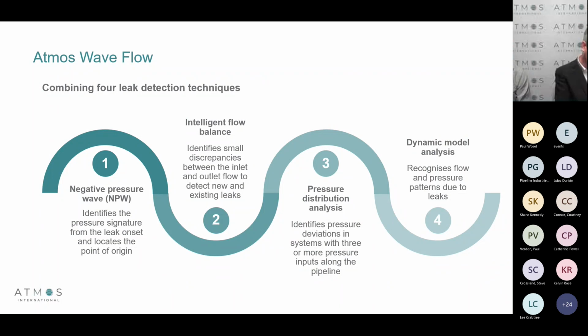The first method is what we call the negative pressure wave. Now this identifies the negative pressure wave when a new leak, burst or rupture occurs on the pipeline. And this will propagate through the pipeline at around the speed of sound, and it will be detected by installed pressure sensors and data acquisition units that are sampling at 60 samples a second. And because we'll be GPS timestamping each piece of data, we can then provide a very good, accurate point of origin.